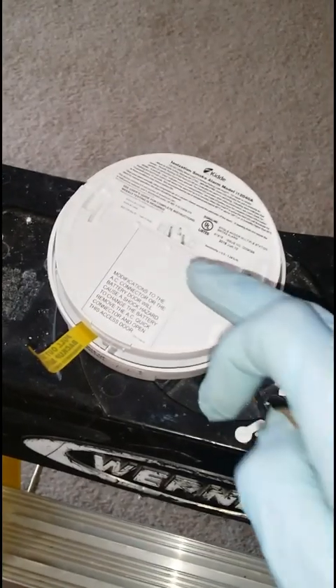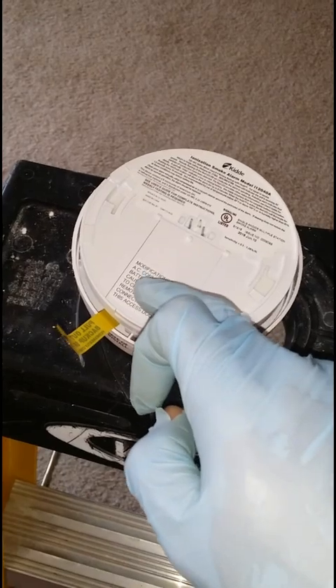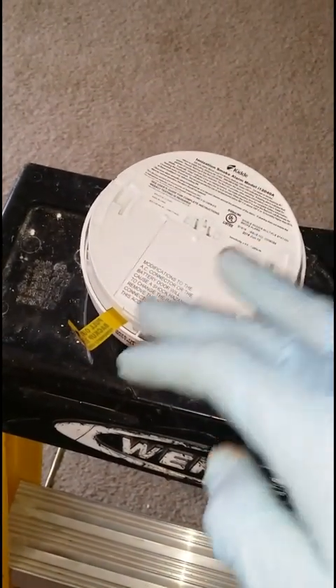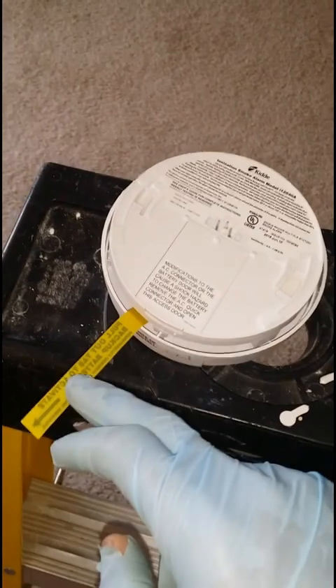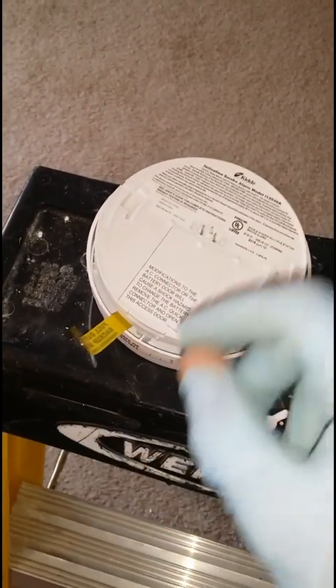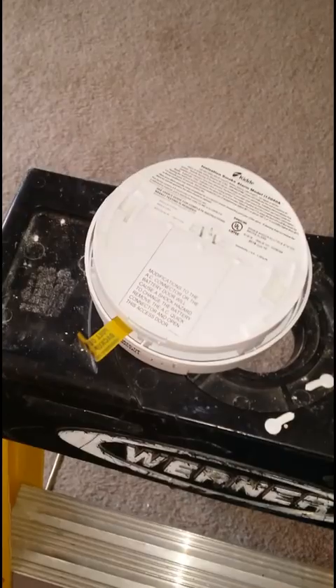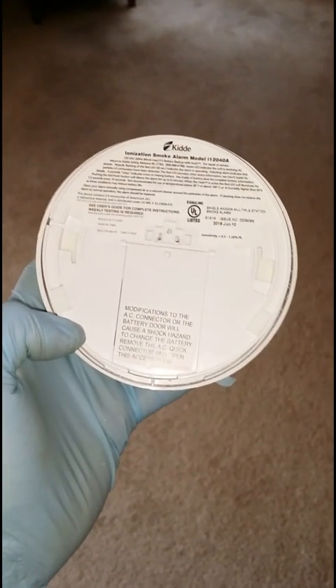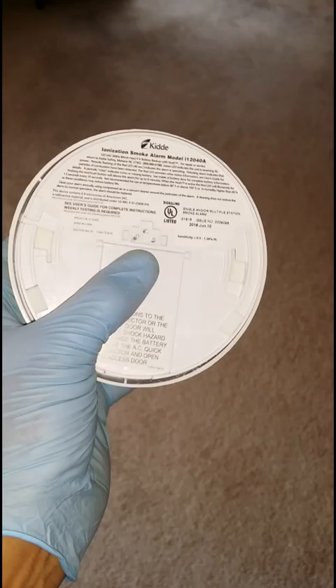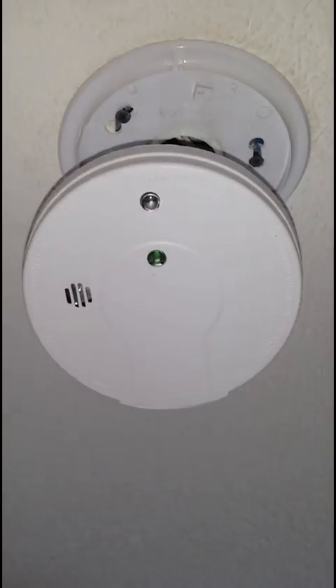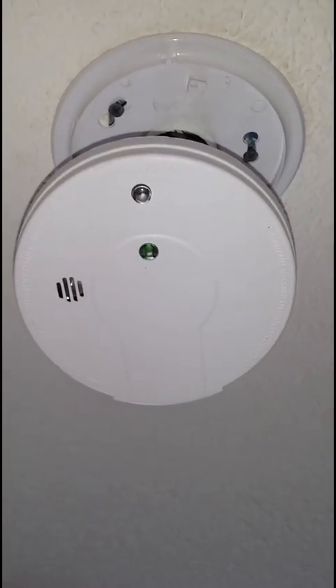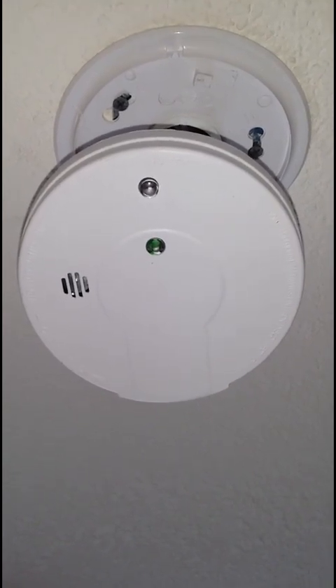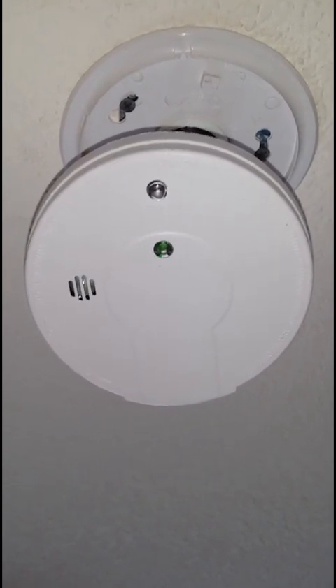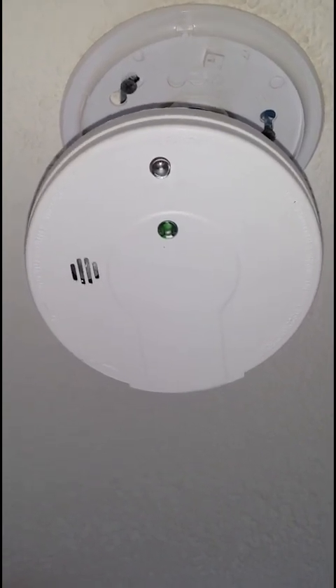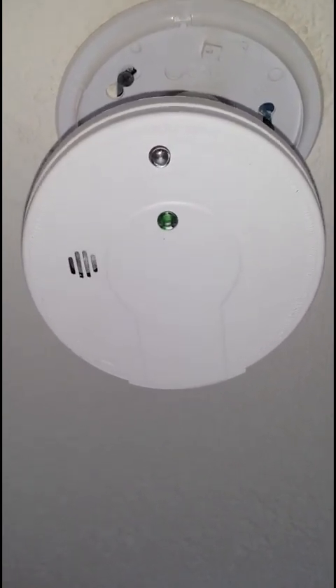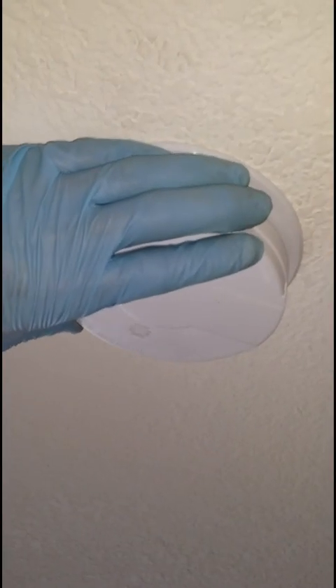Here you can see that the new smoke detector comes with a 9-volt battery already inside. A lot of manufacturers now are having the battery inside in place. They usually have some sort of tab, and once you pull that tab, that will allow the battery to be operational. Once you remove the tab, now you can connect your line voltage to the base of the smoke detector. Once you connect it, you'll see a green indicator light illuminate. You can see here the light is active. And what it's telling you is that it has line voltage powered to the smoke detector. Go ahead and attach your smoke detector to the base.